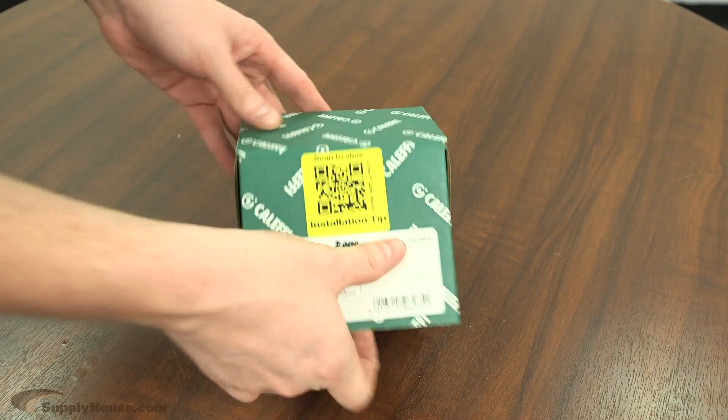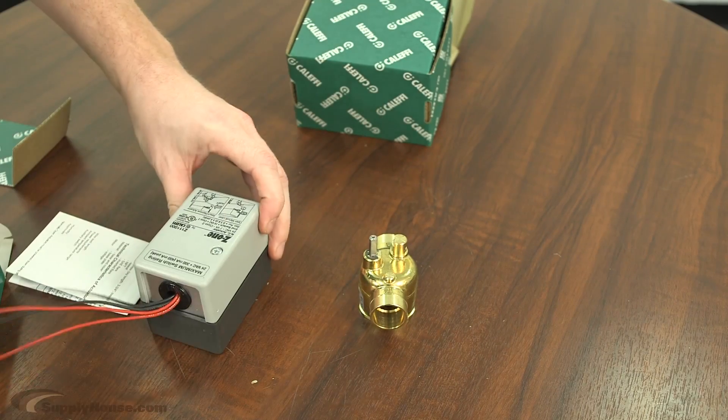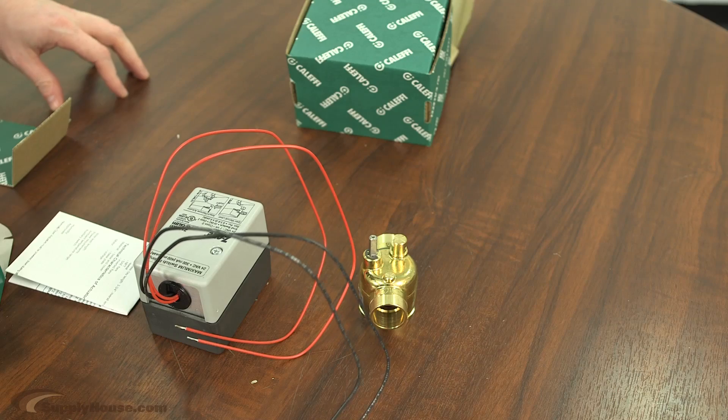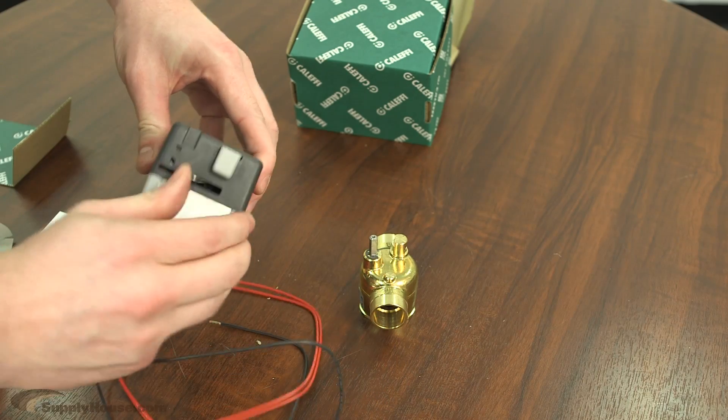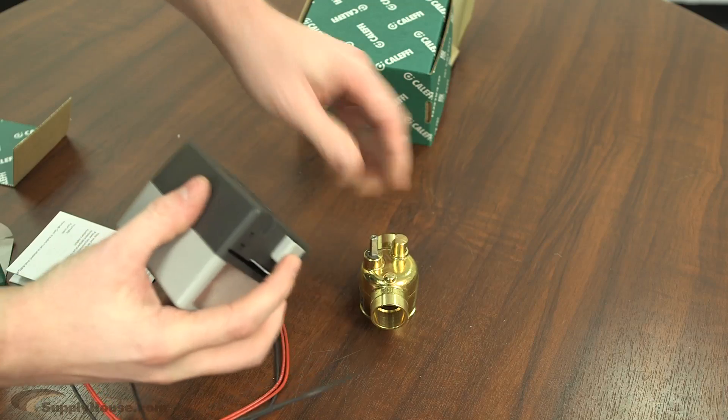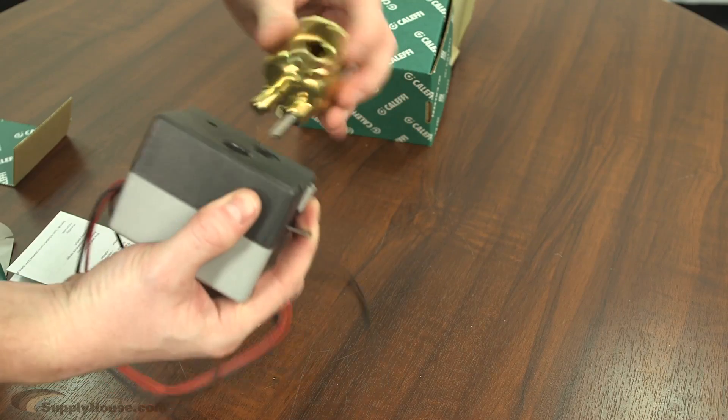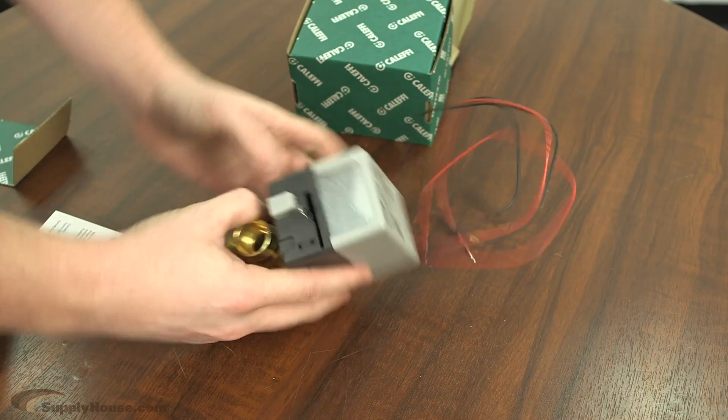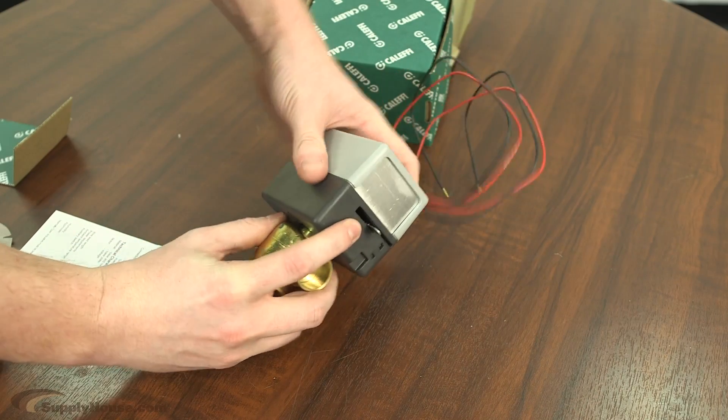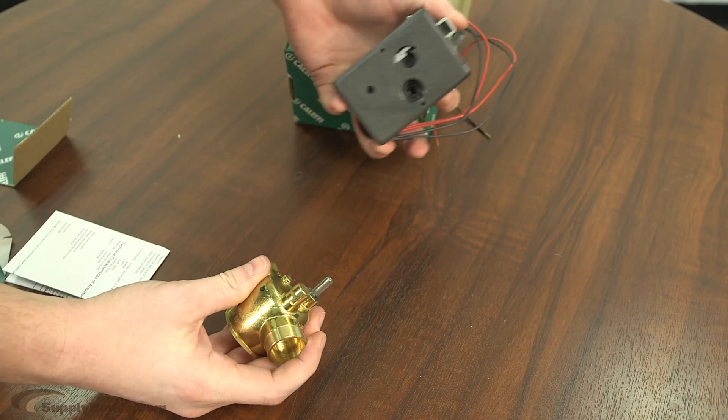Here we have the Caleffi Z series. The valve body and the actuator are shipped separately. These are really easy, too. They're a lot like the Erie. First, you want to lock it open and press the button down. Then you can fit the shaft and the locking mechanism to the valve body. And then to release it, you just depress the button, pull it off, and you're set.